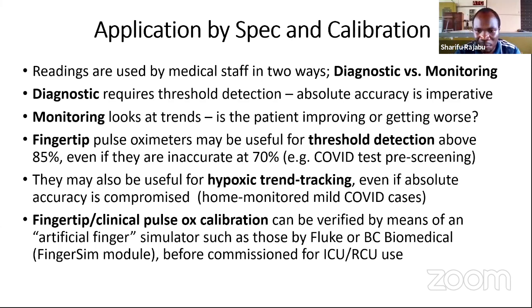They do have a fingertip similar to a finger of a human being, but inside they are filled with a certain fluid. That same fluid is designed to mimic a certain oxygen saturation, but it has been calibrated at a certain temperature. So you might find that during its fabrication, it was calibrated at the environmental temperature of about 22 degrees Celsius. So when you are using a pulse oximeter, you have to consider that also, because even on its specification sheet, they do provide you with a graph that indicates the variation of temperature, how the temperature increases with the increase also in oxygen saturation.